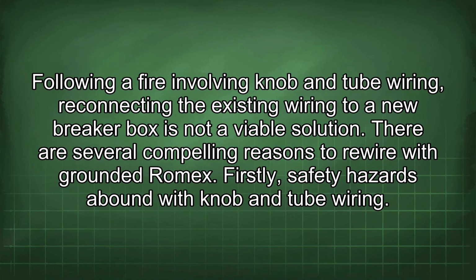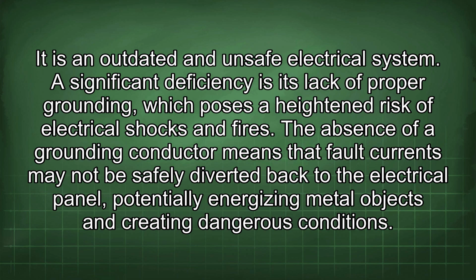Following a fire involving knob and tube wiring, reconnecting the existing wiring to a new breaker box is not a viable solution. There are several compelling reasons to rewire with grounded Romex. Firstly, safety hazards abound with knob and tube wiring. It is an outdated and unsafe electrical system. A significant deficiency is its lack of proper grounding, which poses a heightened risk of electrical shocks and fires.